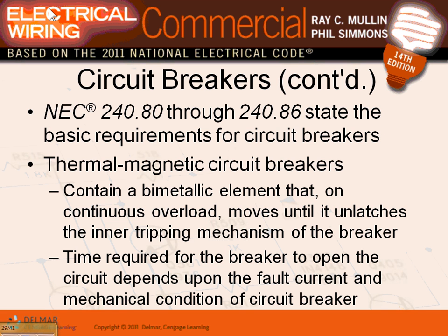Breaker, thermomagnetic. That's for how they design them, guys. How they trip, there are two types of trip for them. There's something called thermomagnetic. It has a thermal component. When it heats up, it trips, right? And also there's a magnetic component. When it sees a very high amount of current for a short circuit, it trips.